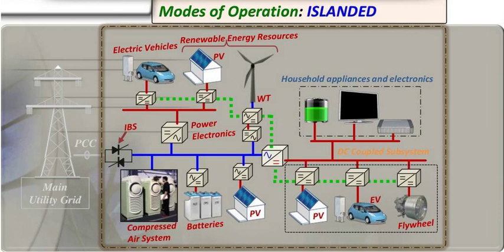Islanding operations, also known as island mode or an islanded grid, occur when a portion of the electrical system continues to operate in isolation from the main grid due to a grid disturbance or a fault in the main grid. This typically happens when there is a sudden loss of grid connectivity due to a fault, maintenance, or a natural disaster, and certain localized areas still have power generation sources available.